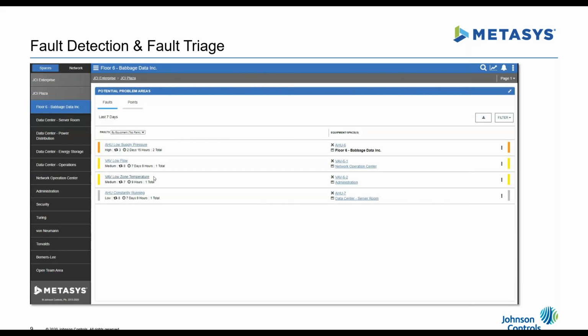Let me describe the difference between a fault and an alarm. Today, Metasys has alarming in both the site management portal and the user interface. An alarm is based on maybe one or two parameters, thresholds, and a delay or two. With faults, there are many more parameters involved, which could be within that system or outside of it, but they're all focused on a certain fault. That's the high level difference between a fault and an alarm.